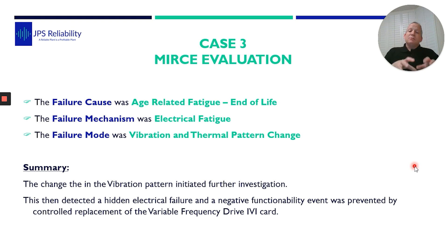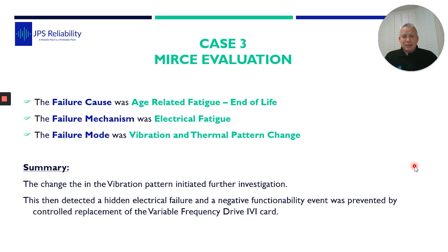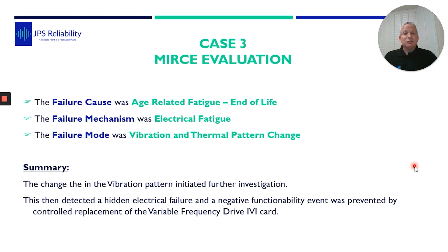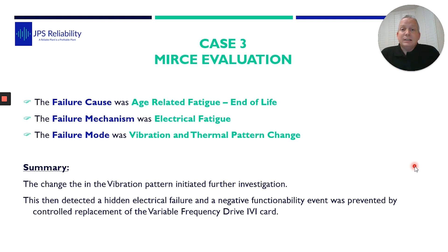So when we're talking about the failure cause and mechanisms — it's electrical. It was a really old drive, been there for a while, so it's more classed as age-related fatigue, end of life. The mechanism of failure: electrical breakdown, electrical fatigue. The failure mode — how we detected it — was through vibration and the thermal pattern. In summary, the change in the vibration pattern and the thermography initiated further investigation, detecting this hidden electrical failure. It was a negative functional event where secondary damage could have occurred, which would have caused production loss and could have caused a motor winding burnout. That was averted, and in a controlled manner they changed the IVI card and it's up and running.